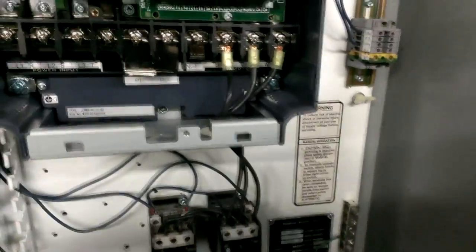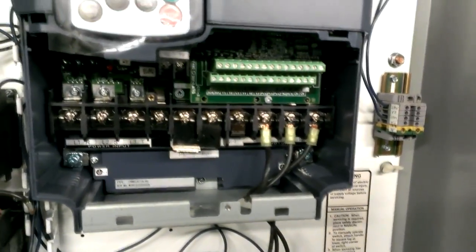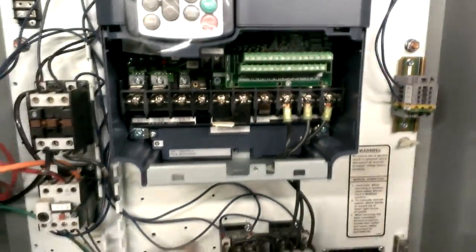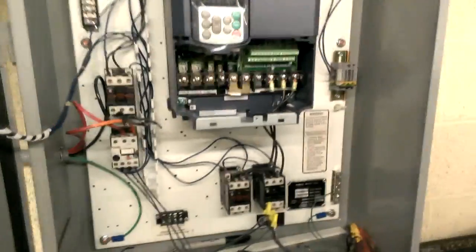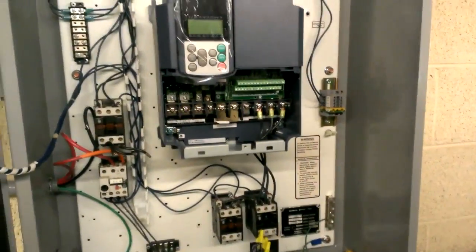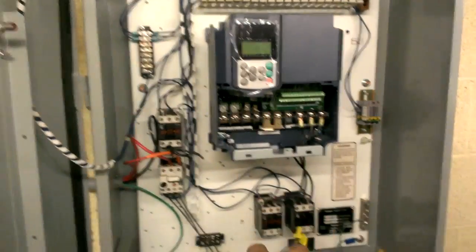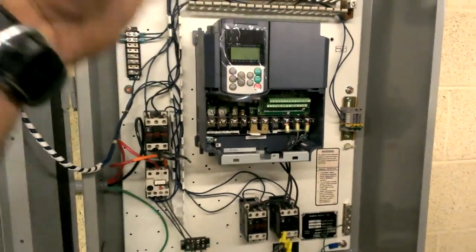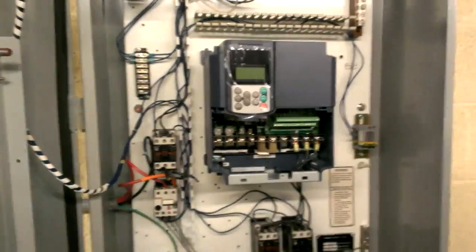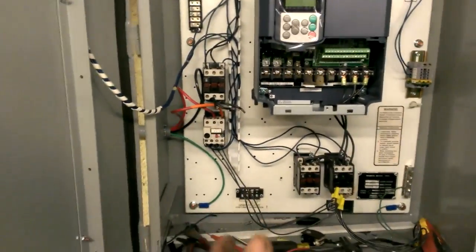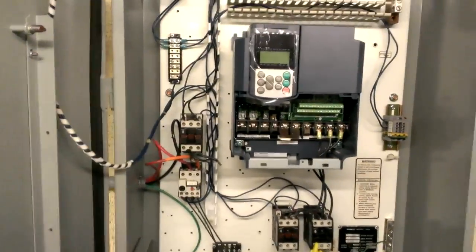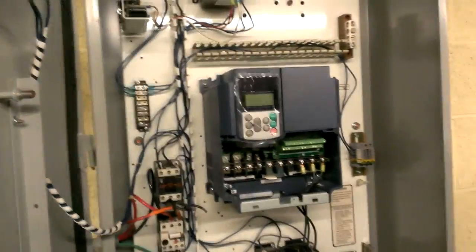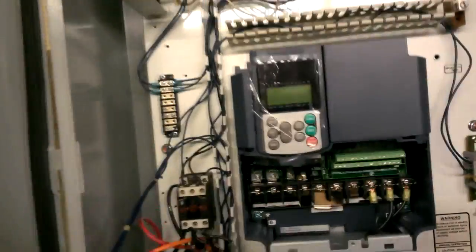I got to be real careful doing that because you don't really want to switch these while the VFD is running, so I'm going to have to do something with controls, some logic to actually switch those, and first shut down the VFD, switch that a couple seconds, switch that back on. This could be another neat little circuit to build.